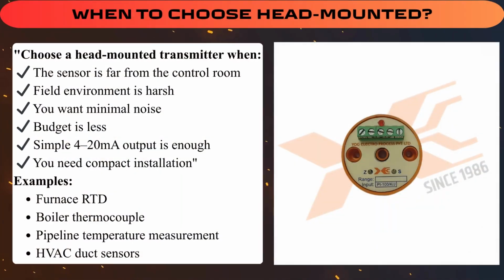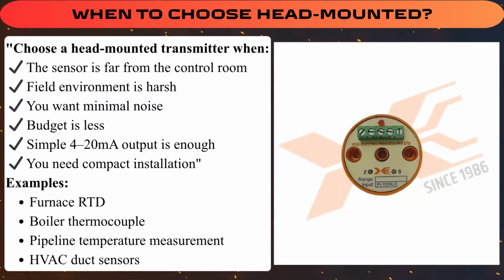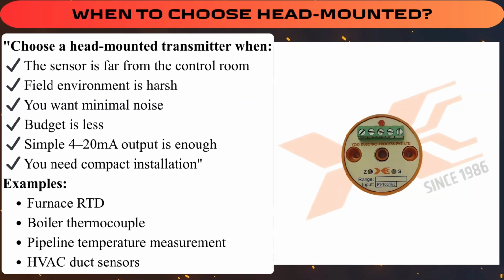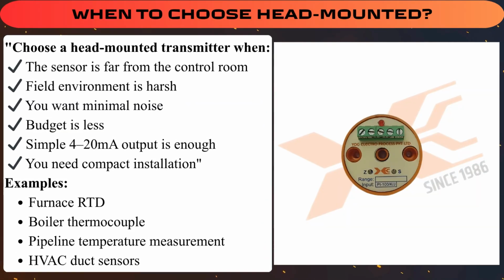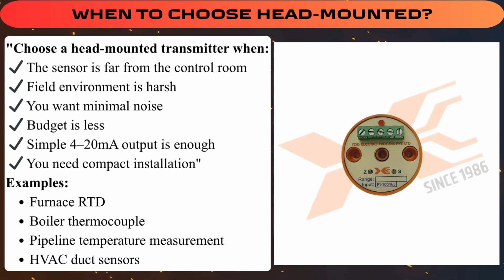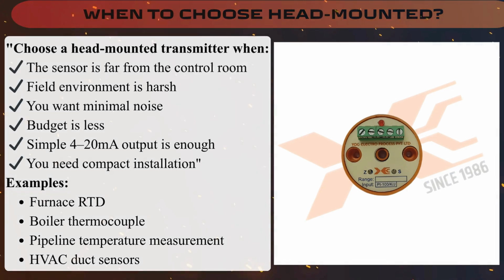When to choose head mounted? Choose a head mounted transmitter when the sensor is far from the control room, the field environment is harsh, you want minimal noise, budget is less, simple 4 to 20 milliampere output is enough, or you need compact installation. Examples: furnace RTD, boiler thermocouple, pipeline temperature measurement, HVAC duct sensors.